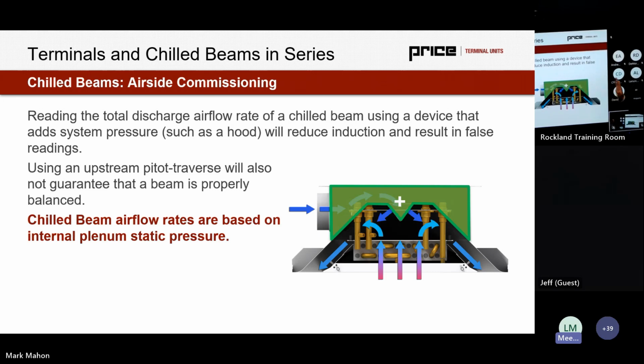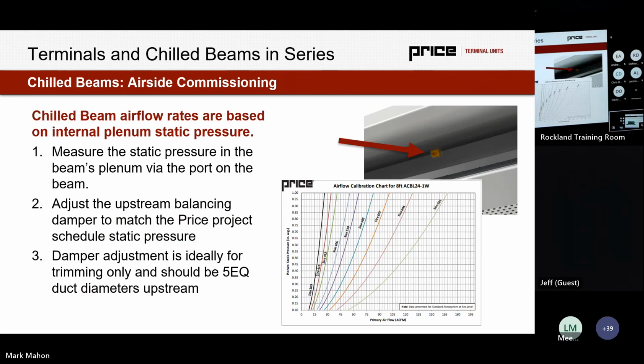And similarly, using an upstream pitot traverse doesn't necessarily guarantee that a beam is properly balanced, and that's true throughout industry, irrespective of manufacturer. We trust the beam's equation. We trust the static pressure in the back pan is going to lead to the airflow delivery rate that we expect. And that's true in industry, irrespective of market, irrespective of manufacturer. So what we would actually end up doing, yep.